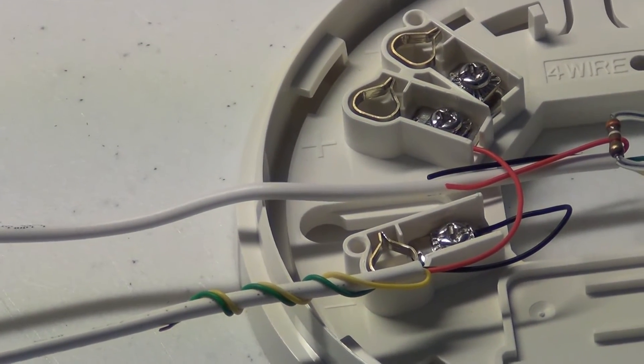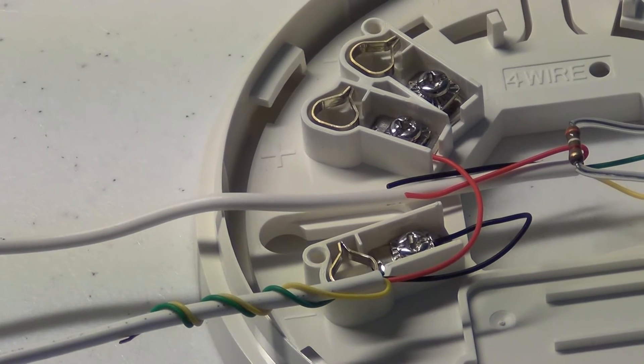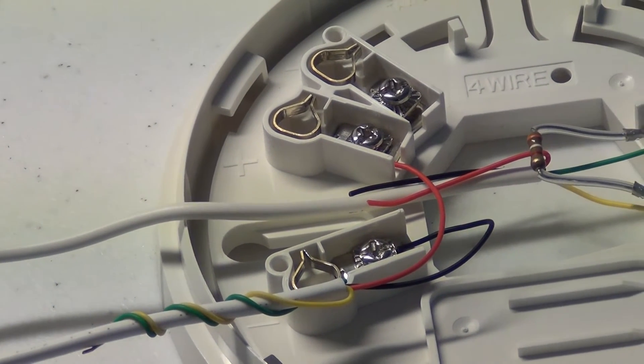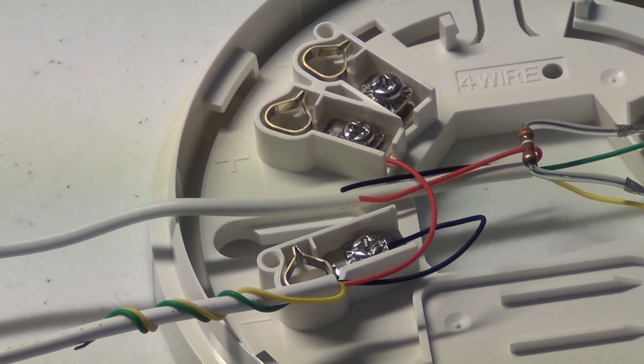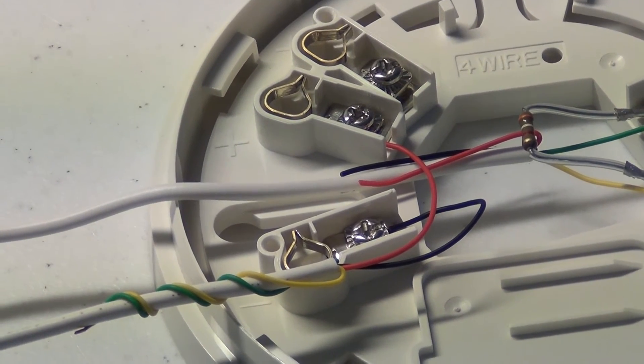If you're familiar with smoke detector hookups you know that they have power wires, two wires have power wires and that's it, and then four wires have power wires and two data wires. So these basically act as your power wires and your data wires.